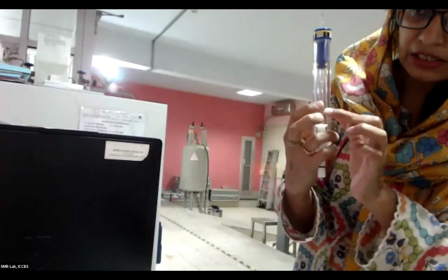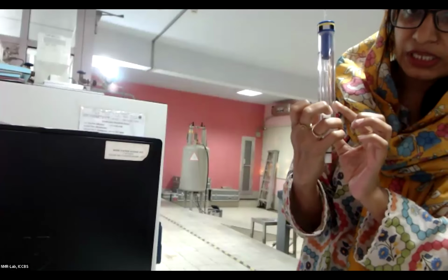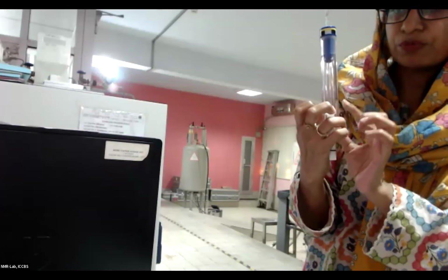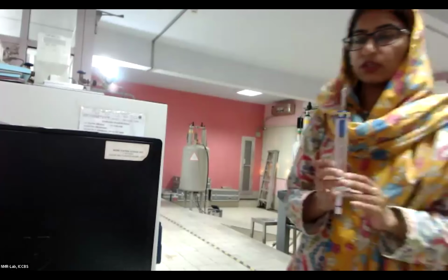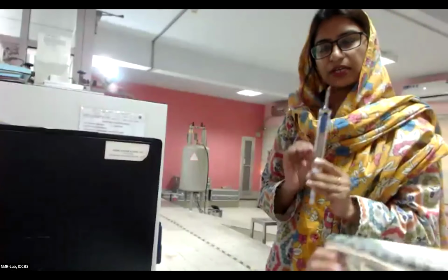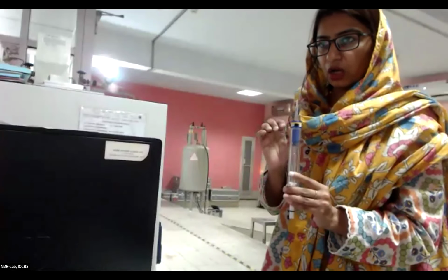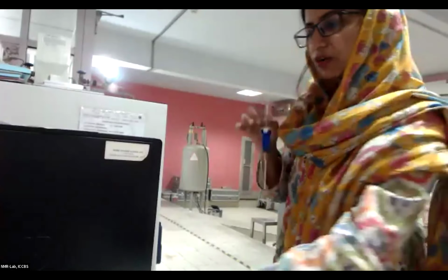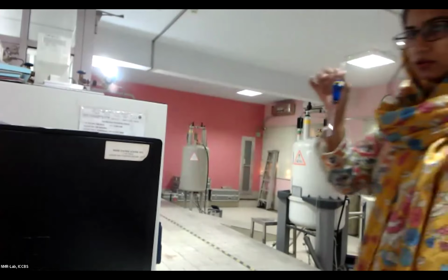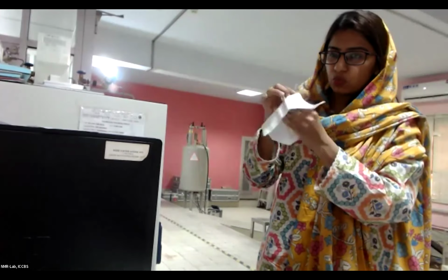Here we have a borderline that is showing the minimum volume of sample you should have to perform the NMR experiment. So right now we have the proper volume of the sample. So we are ready to put this sample tube inside the NMR instrument. And how will we do that? We first take out this tube and we will use a tissue paper, because I have touched it with my fingers. So I'll just wipe the holder.